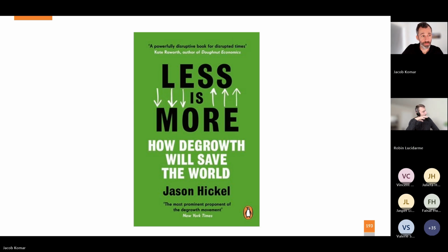One thing I know is, as I highlighted in my slides, everybody talks about energy efficiencies and paybacks based on that. But if you look at operational efficiencies, the numbers look completely different. If you have more data on your building, like the slide Jacob showed, you start at 100% and need only a quarter. Every time you bring demand down, you create less operation and increase operational efficiency, and the payback looks very different than from a pure energy point of view. So we say create your own incentives: more data, lower insurance premiums, lower risk, better maintenance, none of which is put into a standard energy audit equation. Looking at the whole building changes a lot.